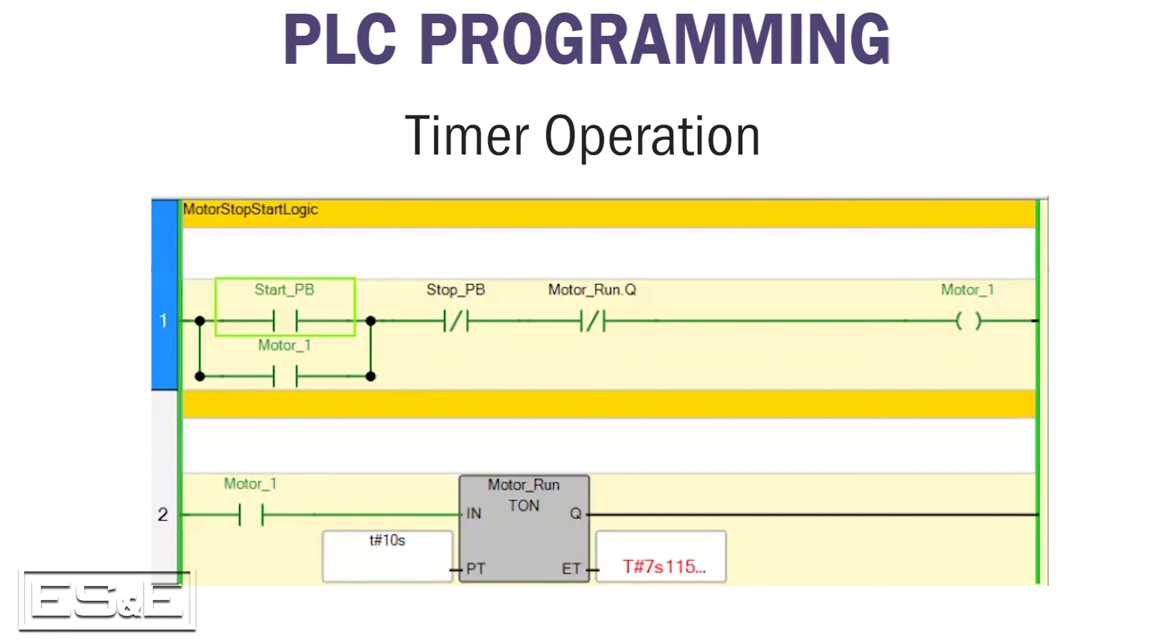On the next rung, motor 1 will be true, which will cause the timer instruction to start timing. When the accumulation value, shown as .ET, is equal to the preset value, shown as .PT, the done bit will change from 0 to 1. In the first rung, the motor will run as long as the done bit is equal to 0. Now that the done bit is equal to 1, the logic solves false and the motor will turn off.